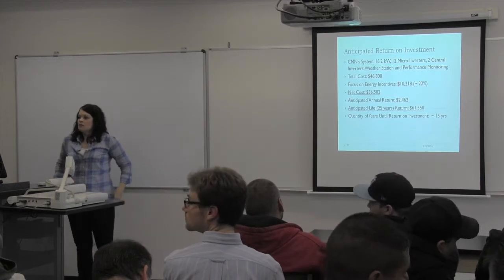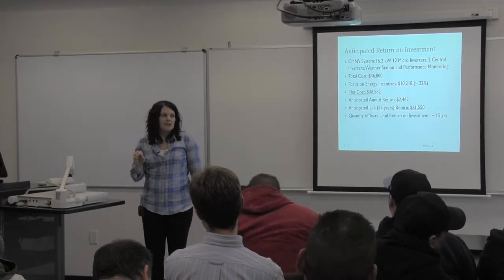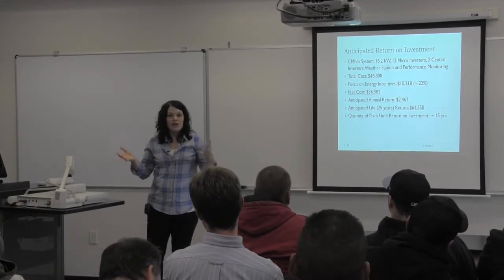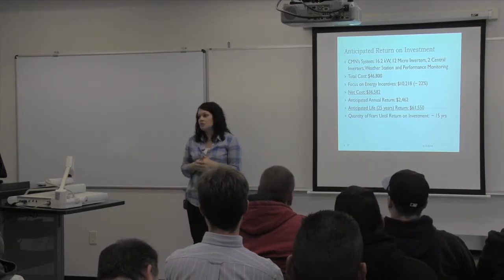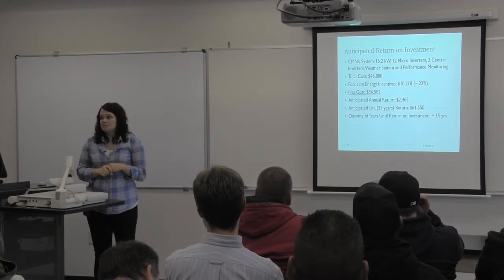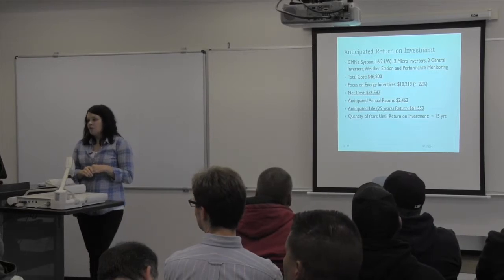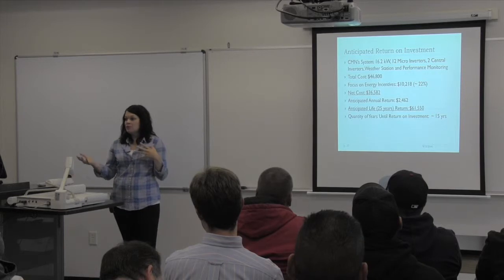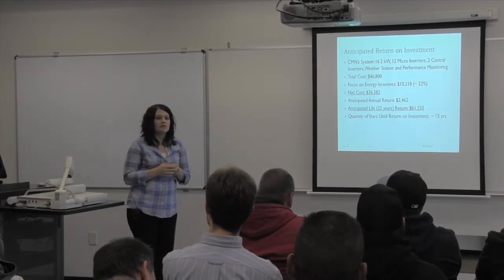What's the longevity? The warranty on solar panels is 25 years, taking into consideration that's 80% at 25 years. So just like your car, you're going to have a warranty on it. That doesn't mean it dies after 5 years. It's just that's what it's warrantied for. So it's warrantied 80% after 25 years. 80% of full efficiency. So if it's rated at 1,000 watts, 80% of that is going to be 800 watts that we can expect after 25 years.